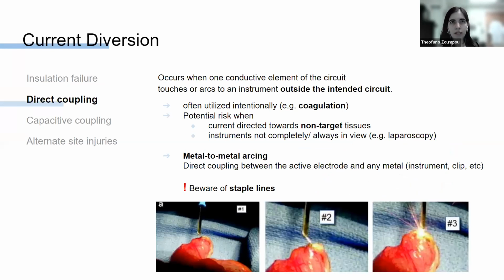Next, we have direct coupling, and this is what happens when one of the conductive elements of our circuit, for example, a laparoscopic instrument, immediately touches or arcs to an element outside of the intended circuit. Direct coupling is often used deliberately, for example, to achieve coagulation. And I am pretty sure you have seen this or you have done this many times in your surgeries. The problem may arise when direct coupling occurs unintentionally, because if the active electrode of our circuit touches an instrument, that whole instrument can become electrified. And that energy might be directed towards non-target tissues and cause injury. The risk for such injury is high in cases such as laparoscopic procedures, where our instruments are not completely or not all the time in our field of view.